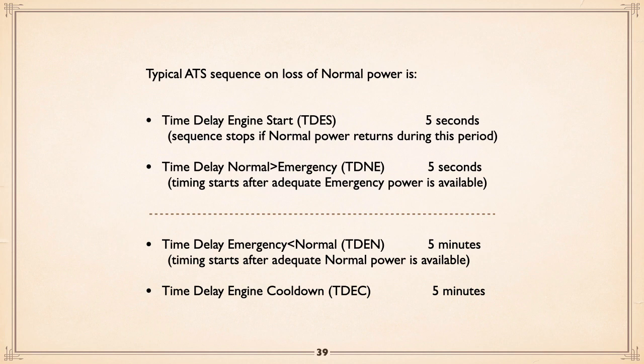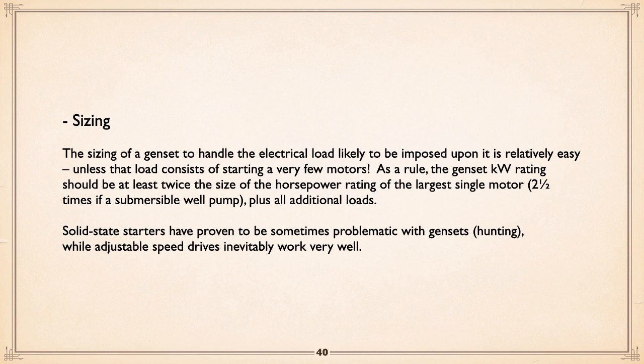When ordinary power comes back, we have another delay, time delay emergency to normal. While before we waited for the genset to come up, in this case we're waiting to see if the utility is for real, or if it just came back as a momentary blip and then fell right back out again. So we wait for 5 minutes. You have to have 5 minutes of normal power there before we flip from emergency back to normal. And then we run the genset for 5 minutes without load to allow it to cool down. So there's your sequence, okay? A genset should be able to handle the load likely to be imposed upon it.